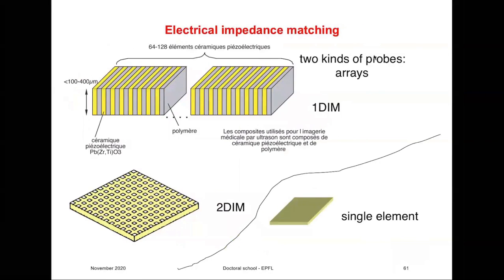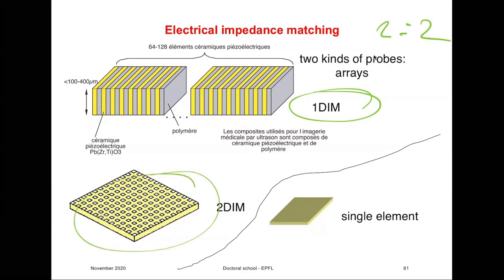Here is an example of a 2-2 composite, and as I said, this is a one-dimensional 2-2 composite, a one-dimensional probe. It can be 32, 64, 128 elements. This is a two-dimensional probe, or if you electrode the whole thing, then you would get a single element.